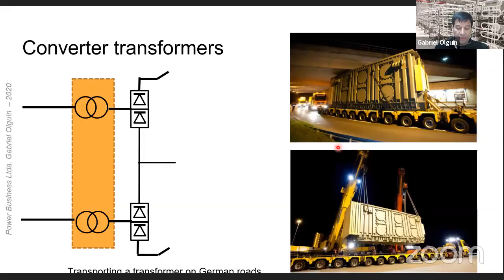Converter transformers. Converter transformers connect the AC bus bar to HVDC converters in the valve hall or valve building. They are needed to adjust the AC voltage applied to the converter valve to optimize the firing angles. It is a 3-phase voltage transformation system, usually made up of single-phase transformers of 2 or 3 windings due to transport limitation. It is the largest and heaviest unit of the converter station, and manufacturing and transport restrictions will determine its configuration and that of the converter station. The size and the weight of the converter transformers pose a challenge that needs to be addressed early in the project development, since it might involve doing works on roads, reinforcing bridges, and so on.